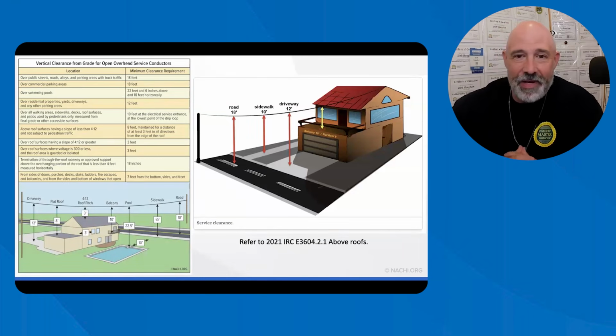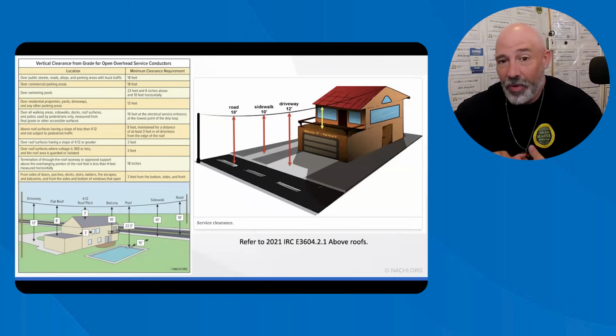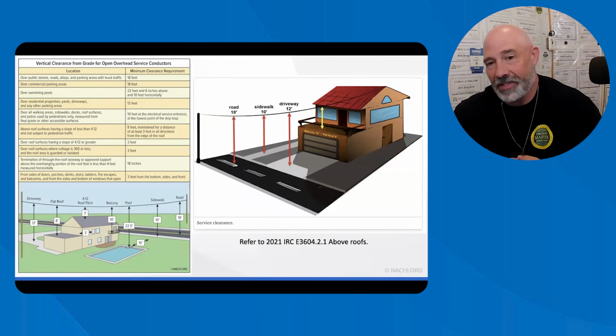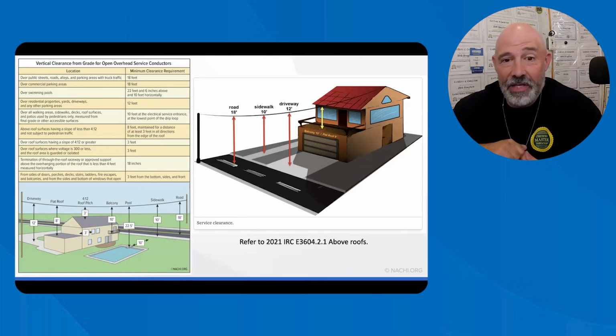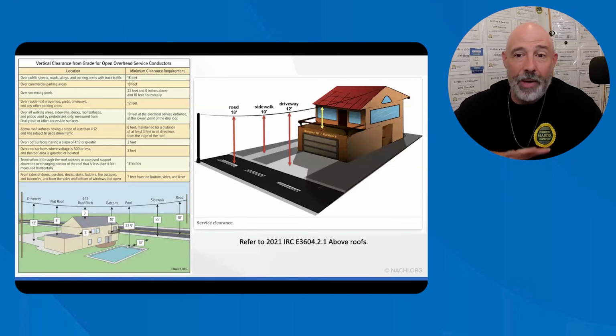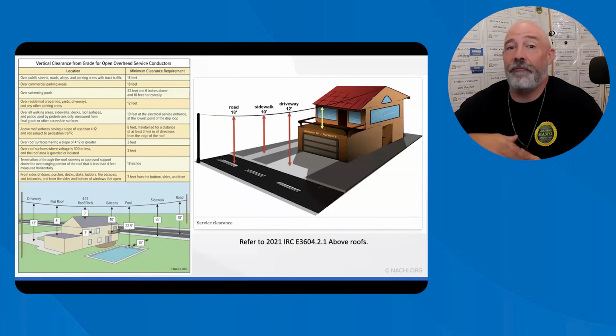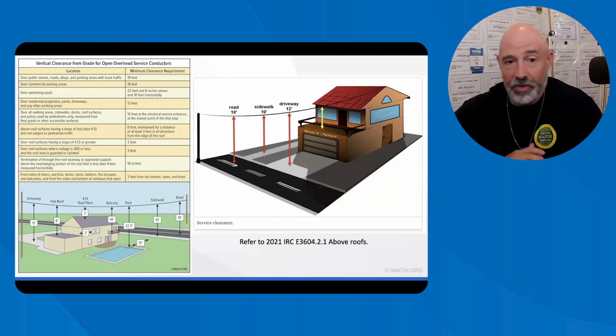Anyways, when inspecting overhead service conductors, remember these common rules. 18 feet over roads and truck traffic, 12 feet over driveways and residential property, 10 feet over sidewalks, decks, balconies, and walking surfaces. 22 and a half feet vertically and 10 feet horizontally from swimming pools. 3 feet from windows and doors and porches and balconies, and so on and so forth, and 8 feet above flat roofs and 3 feet above pitched roofs.